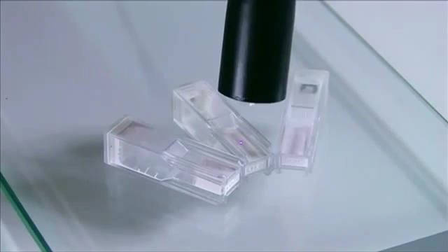In this example, we can clearly see the measurement cycles of the blue LED and the actual measurement processes with infrared. The answer of the lanthanoids to the corresponding emission spectrum are these green segments. What you see here is a sample from before. When I draw closer to it with the sensor head, as you can see, nothing happens quite yet. Only when the sensor head realizes it's resting on the samples does the actual measurement process occur. Now you can see that impulses are being measured and the result will be displayed analogously on the screen. If I draw the sensor away from the sample, the measurement ends.